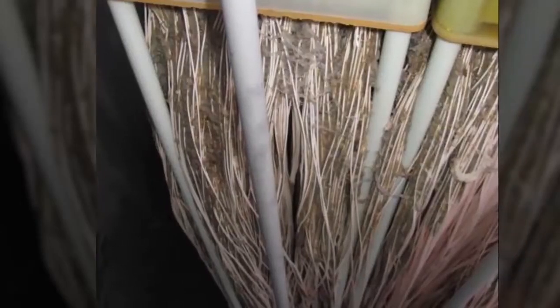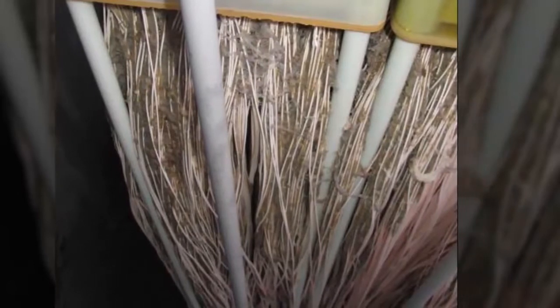There's lint and there's hair. If it passes through the fine screens and gets to the membranes, the construction of the membranes means it'll start wrapping around them, kind of choking them off. Eventually you could have so many of the membrane strands fail that it would cause the entire module to fail, and then we would have to replace that entire module, which is about $5,000. So we are very dependent on the fine screen taking place.